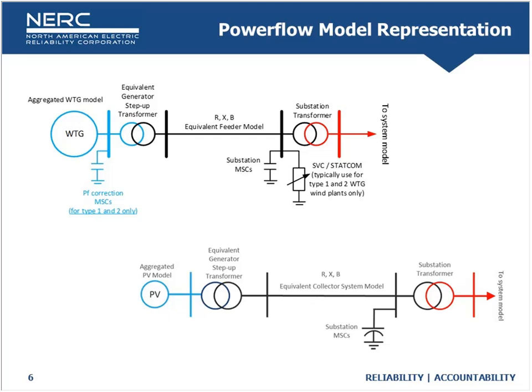The next step we'll be advocating is more advanced intelligence built into the power flow model. When a planner is re-dispatching the wind fleet or solar fleet, for wind Type 2 machines you've got to go in and adjust all the shunt caps every time you make a change to ensure reasonable voltage profiles. When making large-scale dispatch changes, you can end up spending a lot of time with initialization problems. Really, that should all be done automatically in the world we live in today.